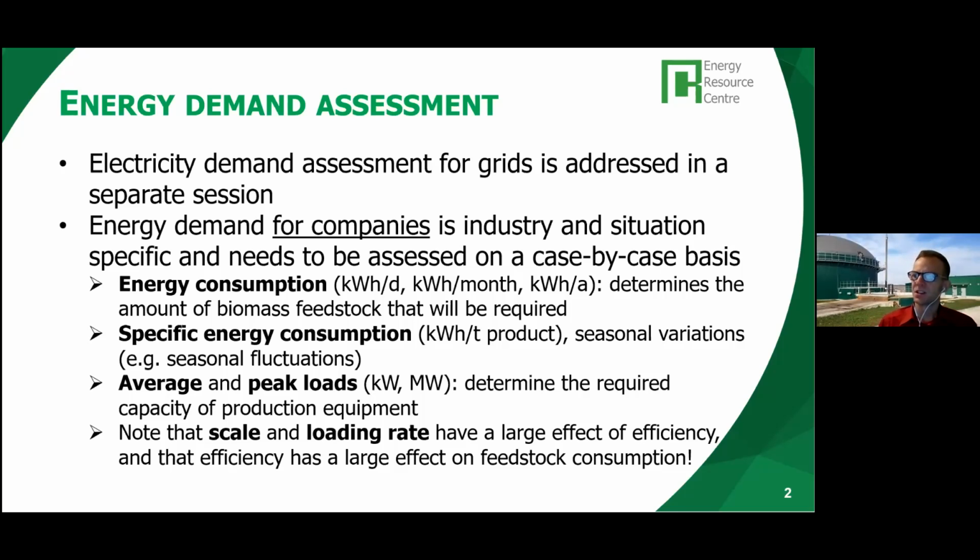Let's say the larger generators, from a few hundred kilowatts upwards, will have a relatively high efficiency of roughly 40% or more, and smaller generators can have a maximum efficiency that is considerably lower, say 35, 30, even 25% for the smallest generators.